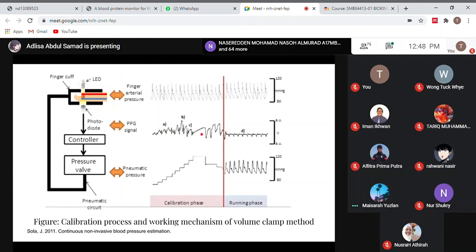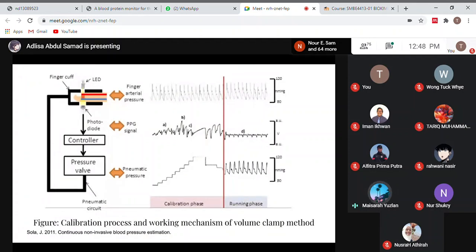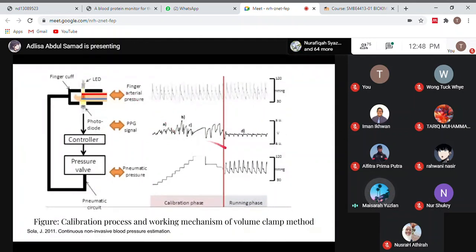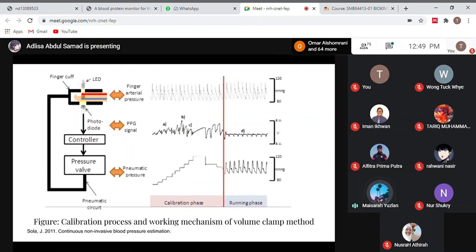So in D, that's when the calibration phase ends. In D, where we see the PPG signal, this refers to the constant blood volume. So the blood volume is constant all around. The pressure valve will continuously clamp and control the cuff pressure to be similar to the arterial pressure. Therefore, the pressure of the pressure valve will equal the arterial pressure, so you will see that the readings are similar. So that's the working mechanism of the volume clamp method.